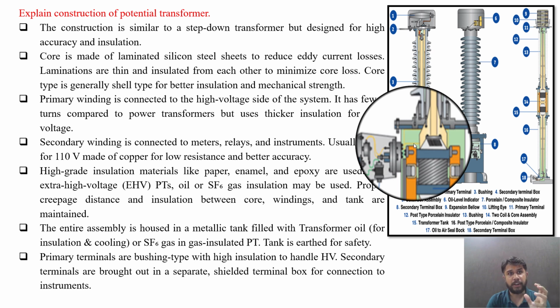The core is made of laminated silicon steel sheets to reduce eddy current losses, and these laminations are thin and insulated from each other to minimize these core losses. Core type is generally a shell type for better insulation and mechanical strength.